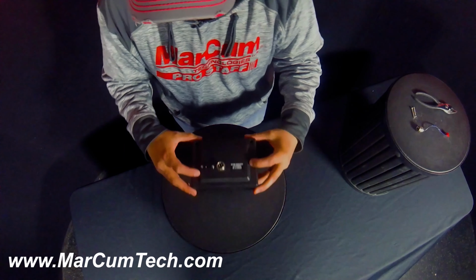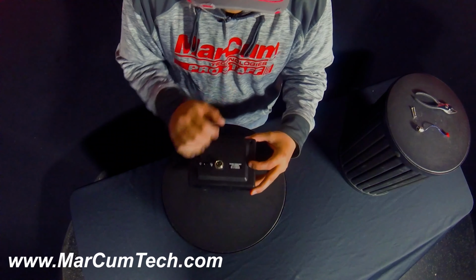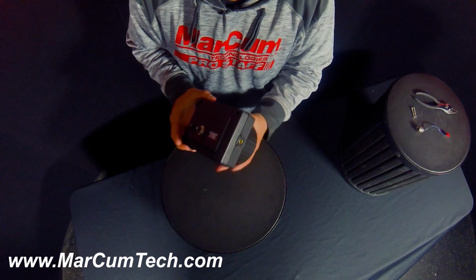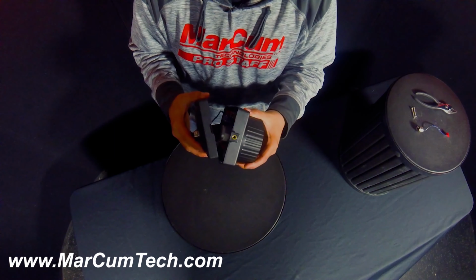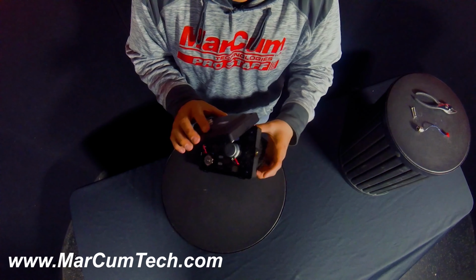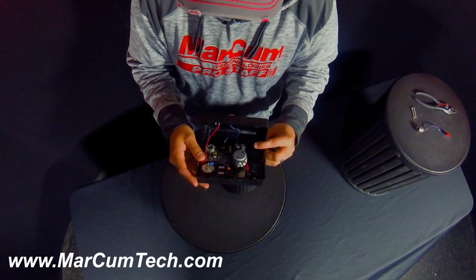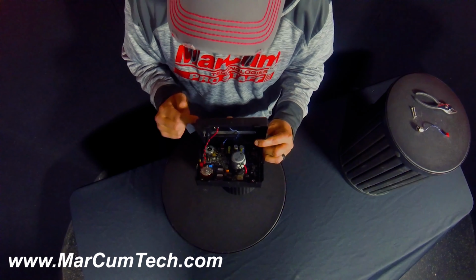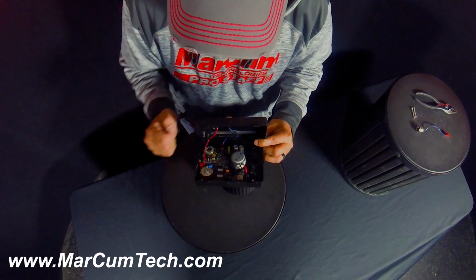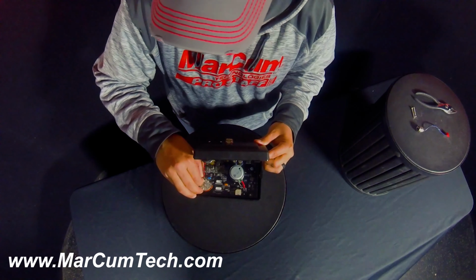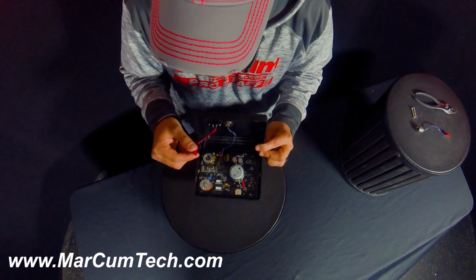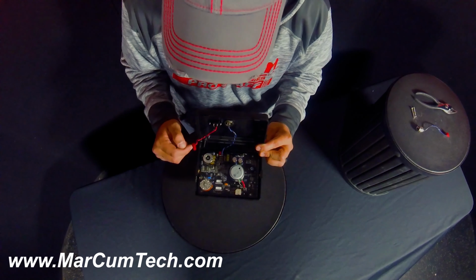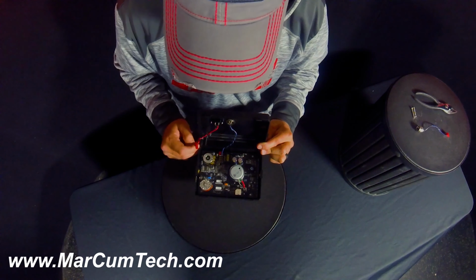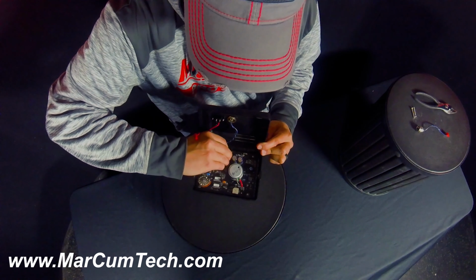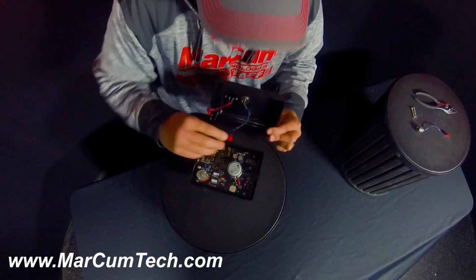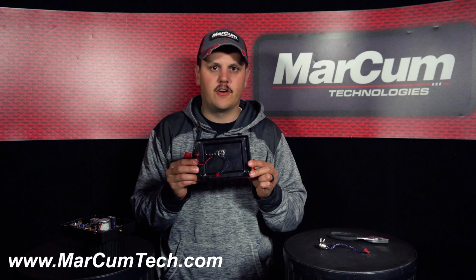And then on the bottom side of that, there's two tabs that you're going to have to undo or pull up, as you'll see here, to get that back piece to come off. So looking at the inside of this system, there's two cords. There's the power cord as well as the transducer cord back there. So I'm going to unconnect that power cord from the board, and that just pulls straight up. And then you can see the transducer cord here, and I'm just going to pull that straight up as well. And that lets that back cover come off.